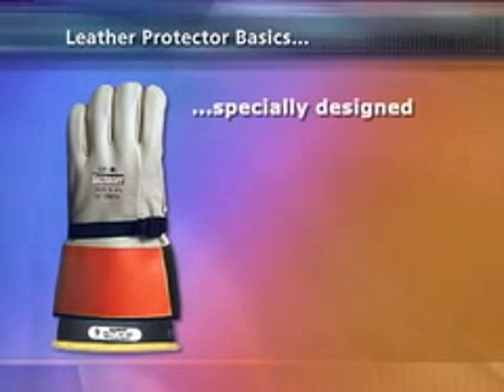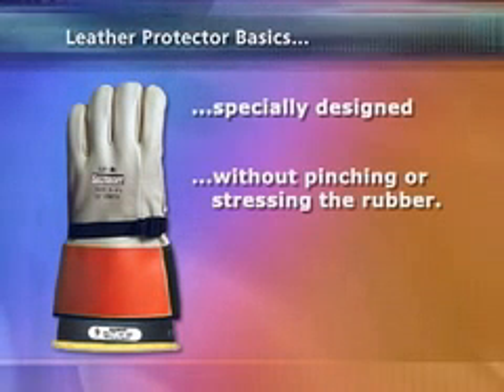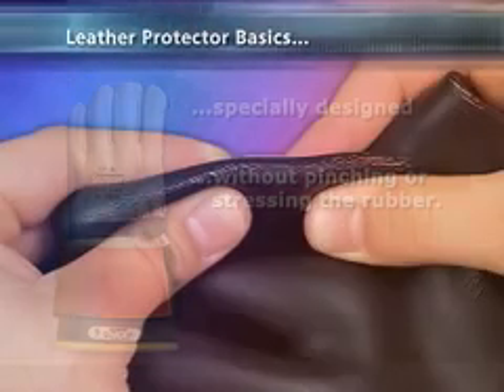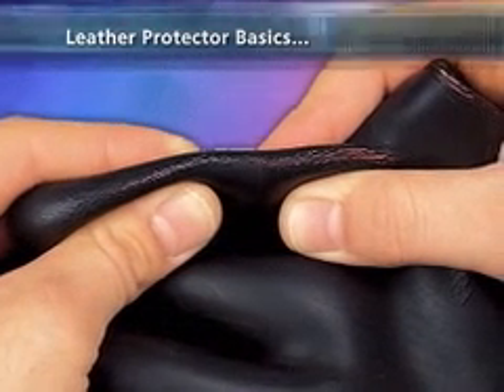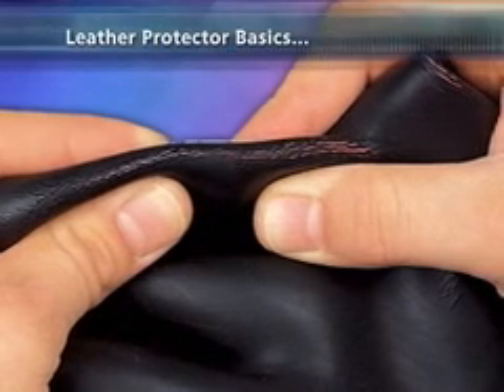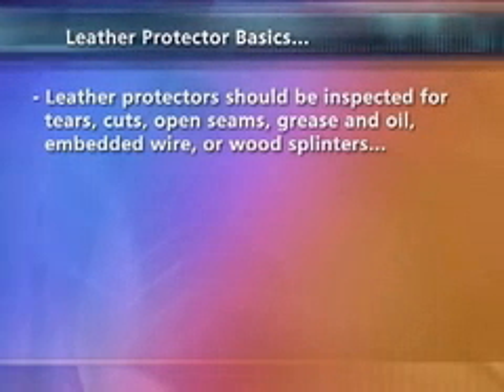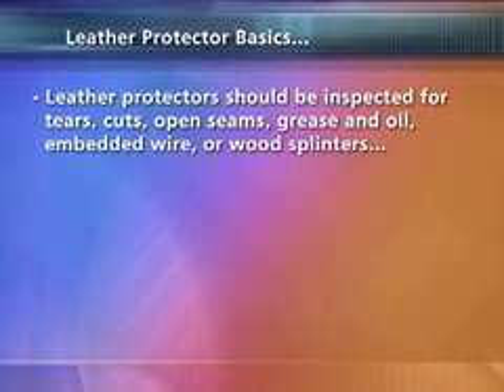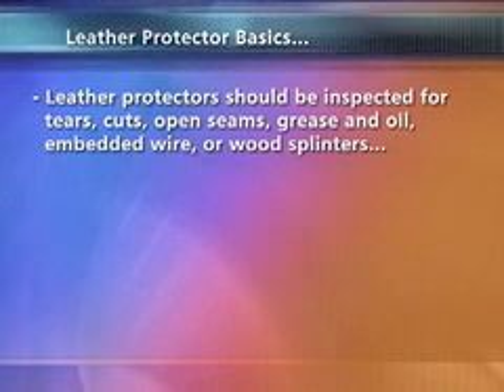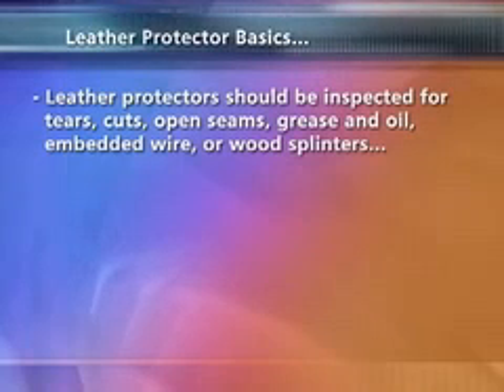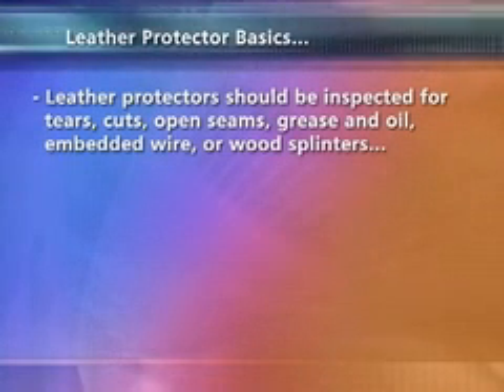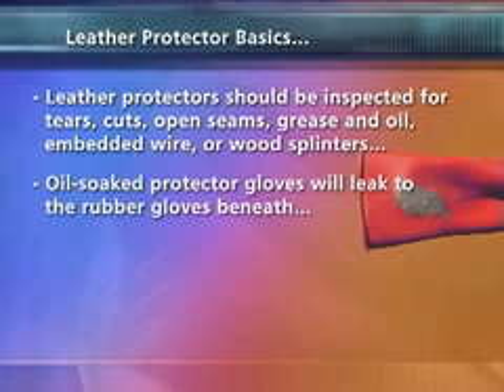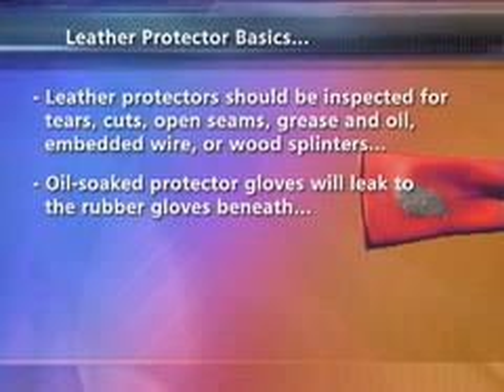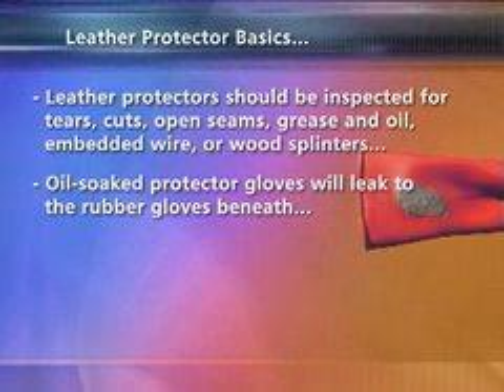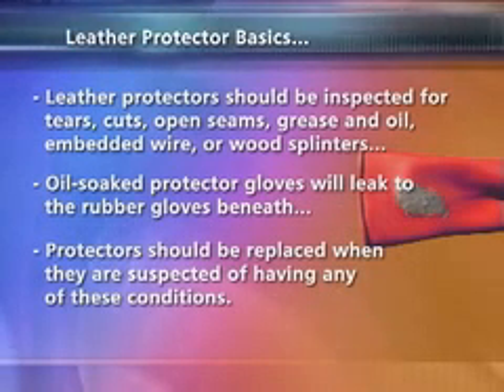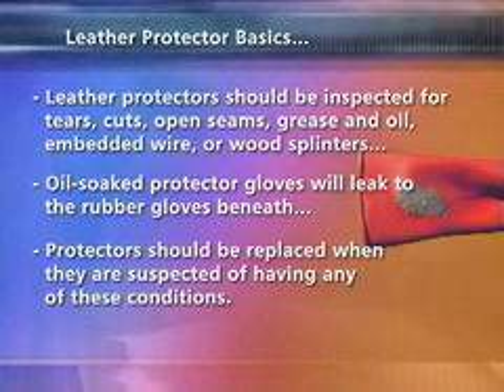Leather protectors are specially designed to fit over the rubber glove without pinching or stressing the rubber. By pinching or stressing the rubber, there is an increase in the likelihood of damage from ozone. Leather protectors should be inspected for tears, cuts, open seams, grease and oil, embedded wire, or wood splinters that could possibly come in contact with the rubber gloves. For example, oil-soaked protector gloves will leak to the rubber gloves beneath, causing them to be damaged. Protectors should be replaced when they are suspected of having any of these conditions.